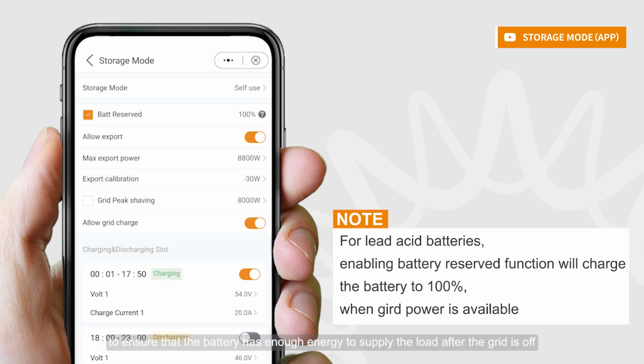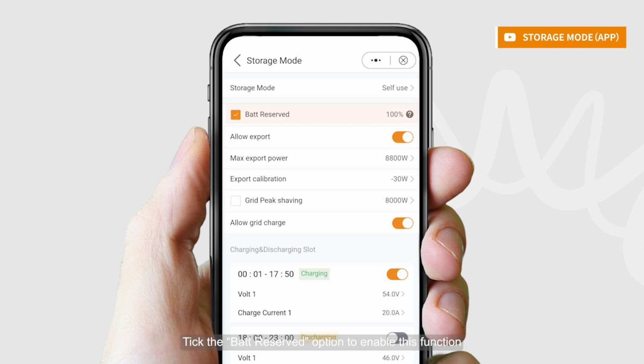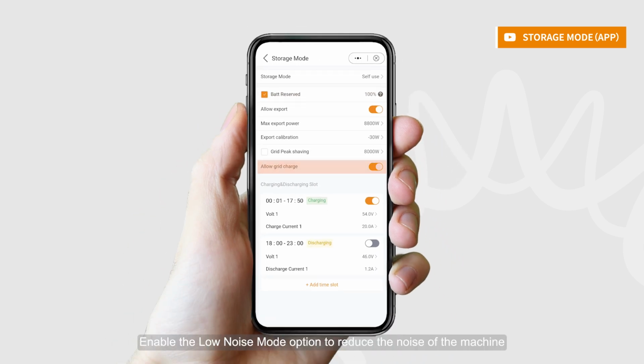Set the battery reserved parameter as needed. The recommended value is more than 80% to ensure that the battery has enough energy to supply the load after the grid is off. Tick the Batt Reserved option to enable this function. Tick Allow Grid charging option to allow the battery to be charged by the grid power.